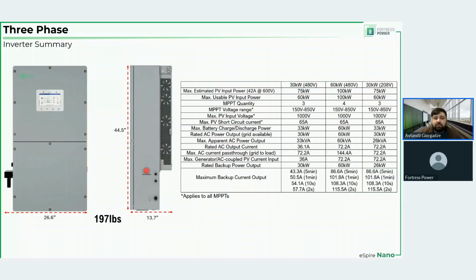So for example, if you have a 30 kilowatt 480 volt unit and you want to connect a generator to it, rather than capping the generator input or generator output to 30 kilowatts, we might in the future allow 120% of that 30 kilowatts. But again, this is just an internal conversation. I don't know what the final conclusion will be and whether or not we implement the change.